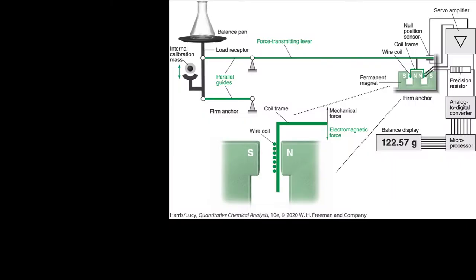The operation of an analytical balance is quite complicated, and so this diagram gives us a simple idea. We've got our balance pan that we place our object on, and there's a series of beams inside that will transmit the force. So for instance, the weight pushes down here and it's transmitted to this beam here, which causes this lever to increase in height.